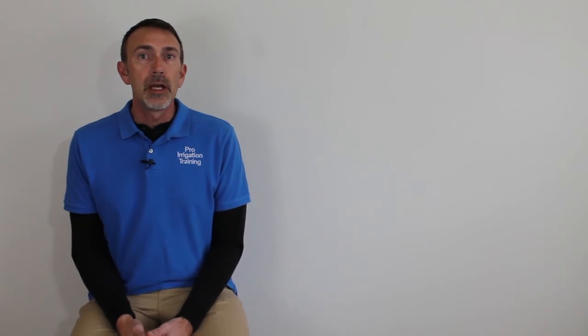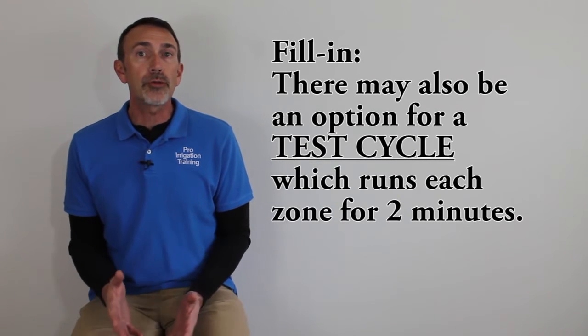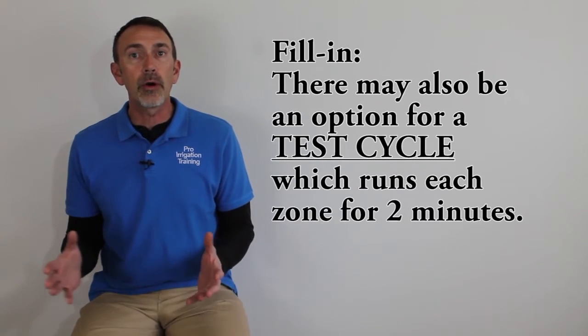So as a technician and you're going out to do an inspection or adjust some heads, we're almost always going to be using the manual feature on these timers. Some timers have the capability to run what's called a test cycle, which will go through and run each zone in order for maybe two minutes.